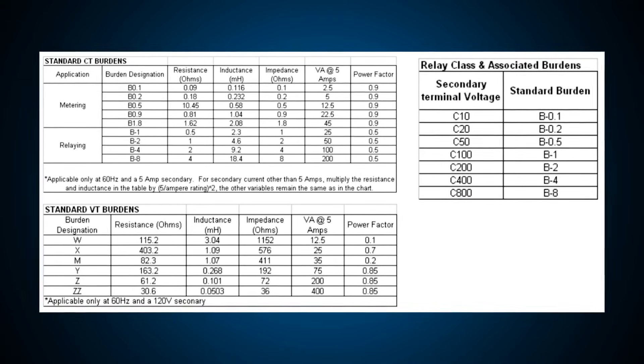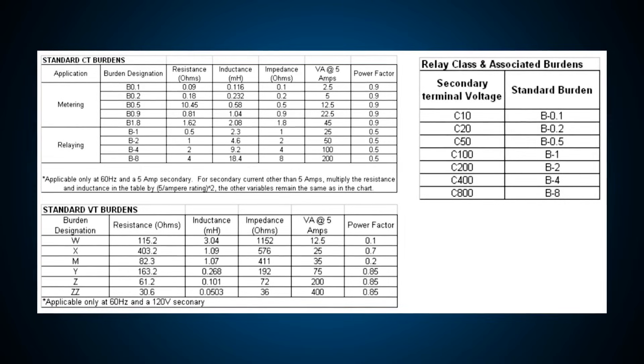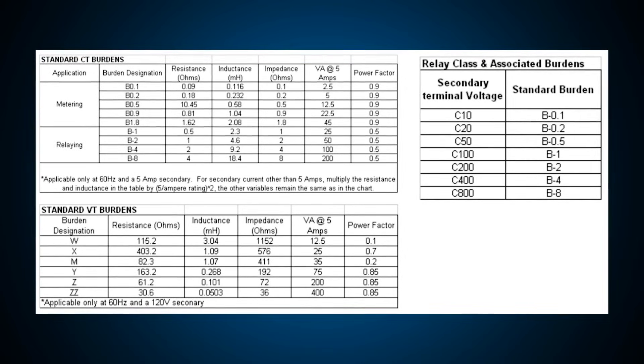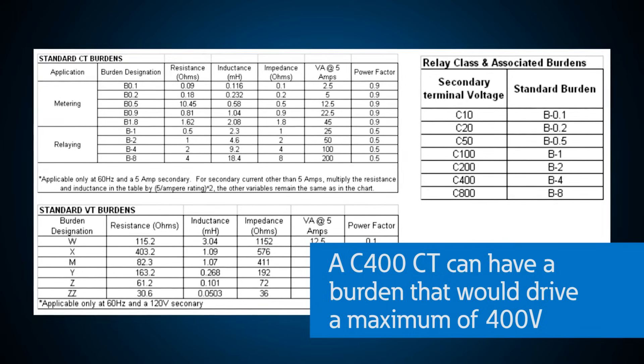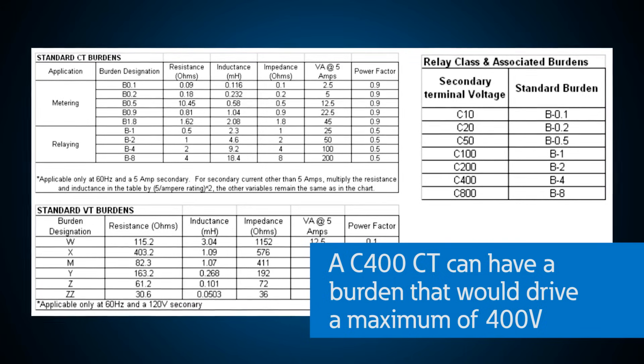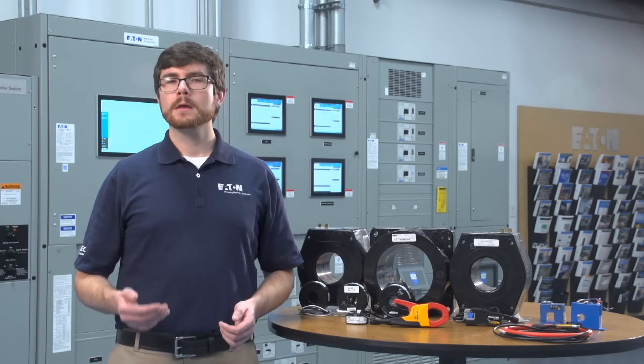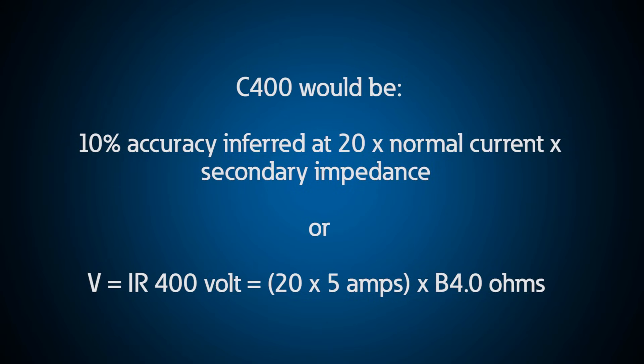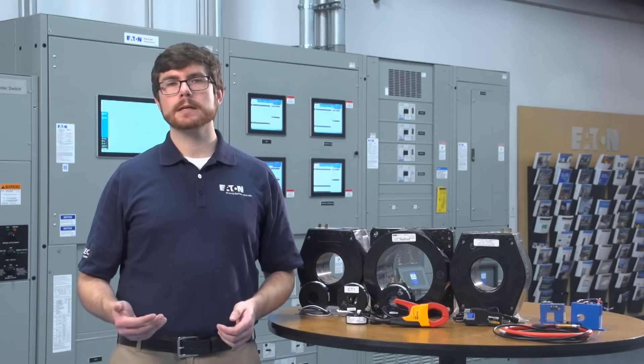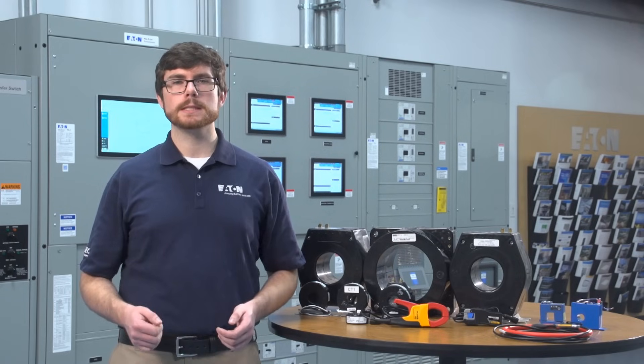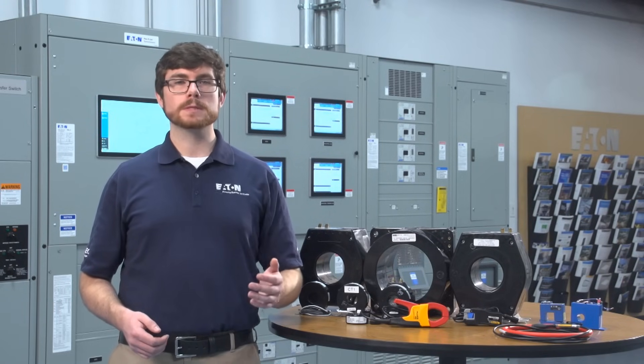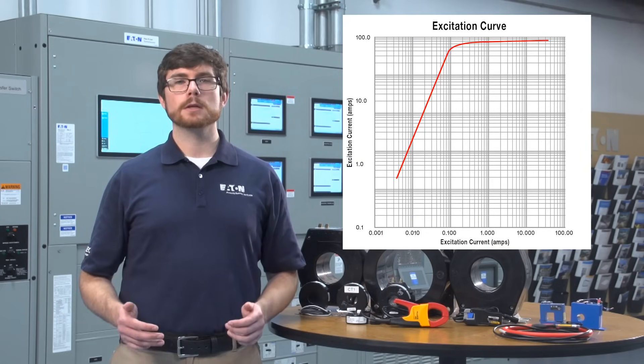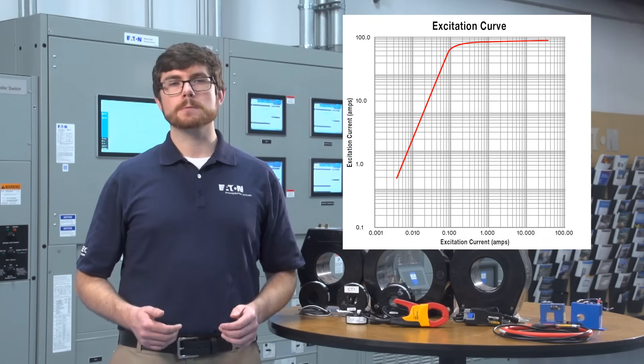In simple terms, this means that a CT with a higher rating can sustain more burden on the secondary without saturating. For example, a C400 current transformer can have a burden that would drive a maximum of 400 volts. Based on these tables, a C400 would have an error of no larger than 10% at 20 times normal secondary current with a secondary burden of 4 ohms. Manufacturers will often offer a graph of the excitation performance of a particular CT. The graph allows you to determine the performance of the CT over the entire range of secondary current and ensure that the CT will function as required.